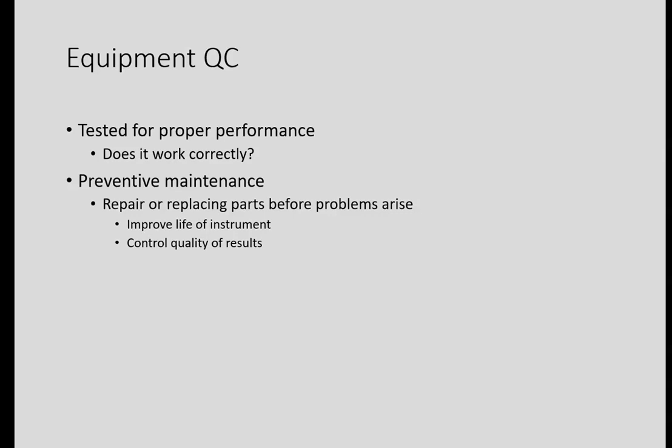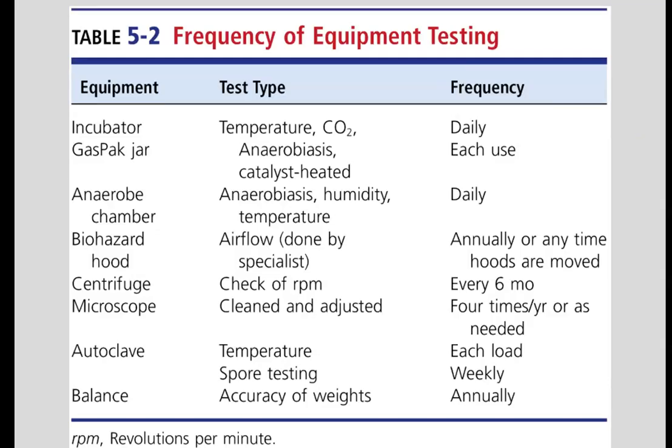If someone slams a micropipetter or drops it from the countertop to the ground and it hits pretty hard, the calibration may be off. You should really check that. For equipment testing, you're going to check your incubator every day. If you have a GasPak jar — the jars are kind of outdated but not so much.